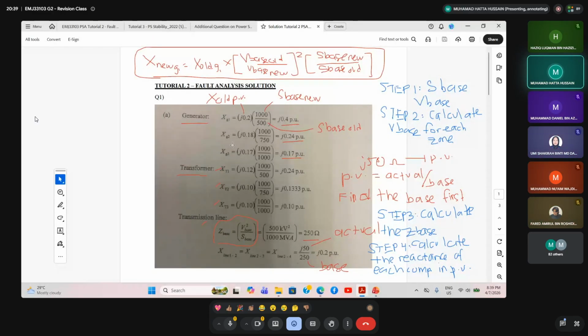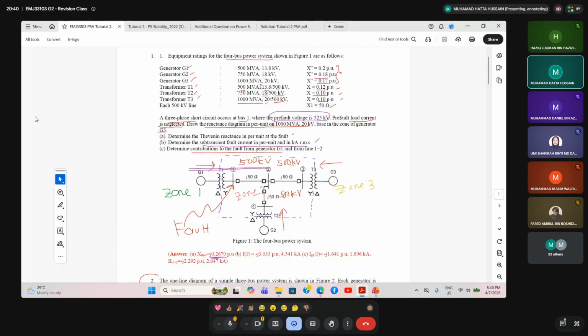And then for xg2, referring to this value here, the reactance is J0.18 per unit. You just write this value, then multiply times 1000 divided by 750, which gives J0.24 per unit.